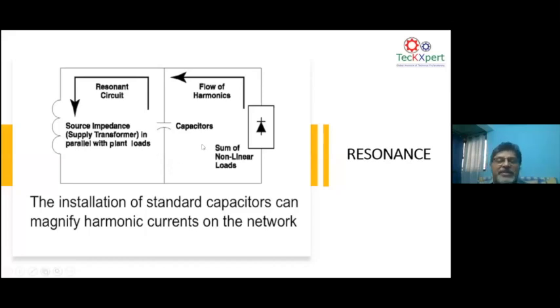Now in a conventional equivalent circuit, you will see the capacitance sitting in parallel to the rest of the inductive impedance. And if you have harmonics flowing from this VFD or a nonlinear load, at the point of resonance these two become equal and opposite. Now, when XL and XC become equal and opposite, in the equivalent circuit you will see the denominator has a zero value. XL and XC become equal and opposite, the denominator becomes zero. That means your current becomes infinity. So that is how parallel resonance causes infinite current.